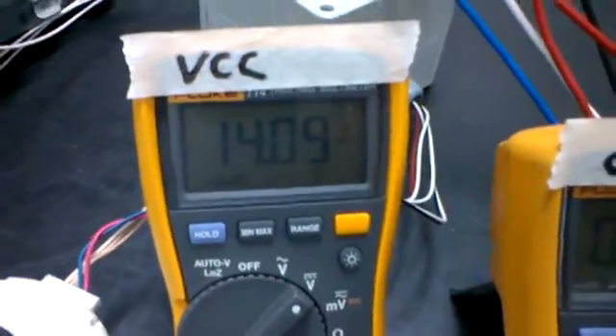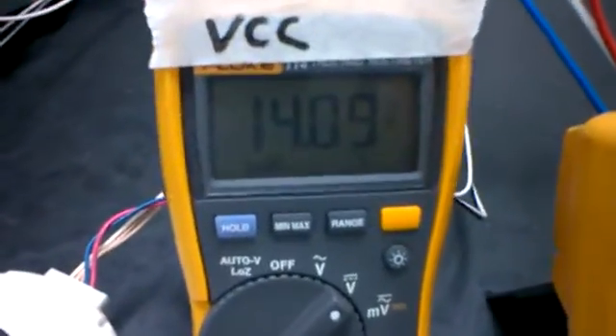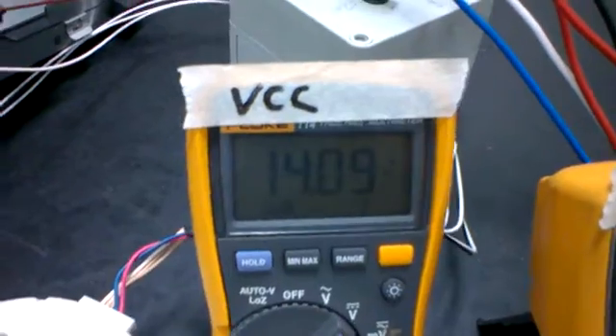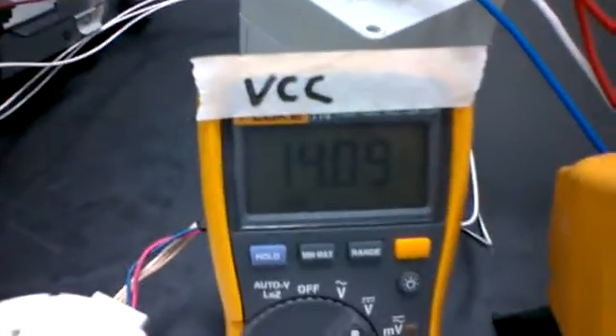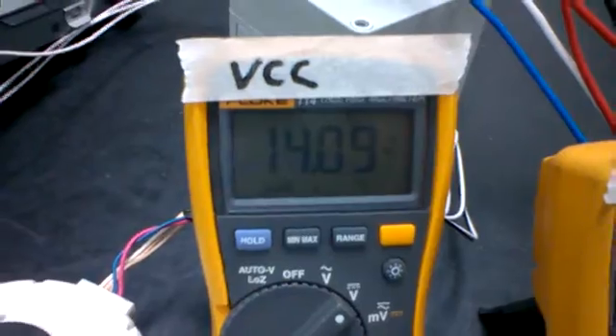Now the first one is the VCC which you can think of as a supply or a control voltage. This basically allows the motor to function internally with its own little microcircuitry inside. Now without this signal, and in this case we're looking for around 15 odd volts, nothing runs. If the PCB does not generate this out to the motor, it does not work.